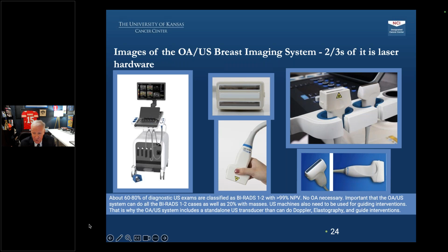This is a close-up of the probe. The ultrasound frame rate is anywhere from 20 to 50 frames a second. The laser pulses are fired at 10 pulses per second because we have to allow enough time between the pulses for the heat generated by the very brief energy laser pulses to dissipate, to diffuse to the surrounding tissue, and also to be carried away by the flowing blood. Most of what's getting heated is the blood, but as the blood flows, it carries the heat away.